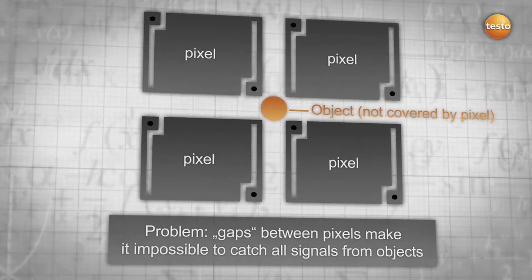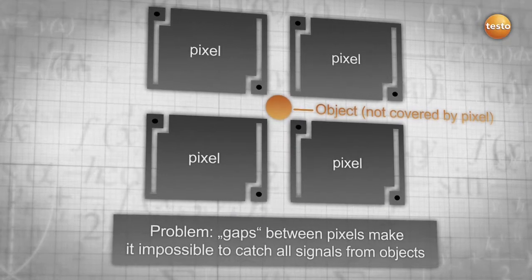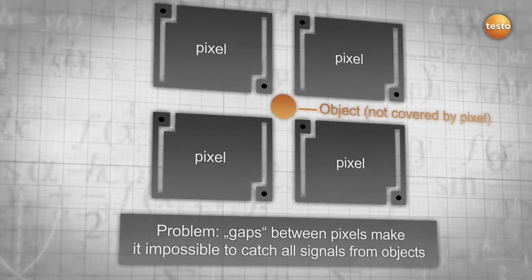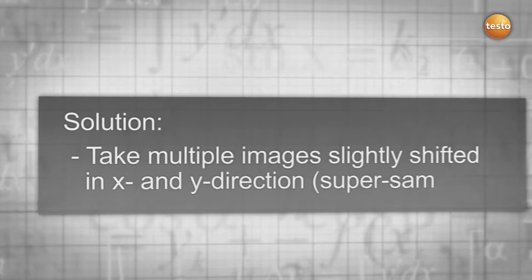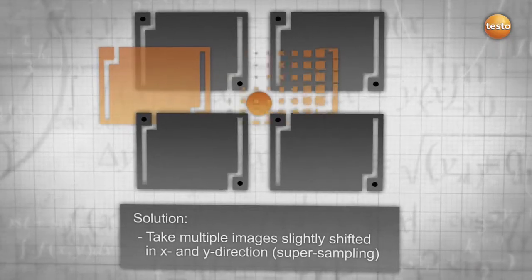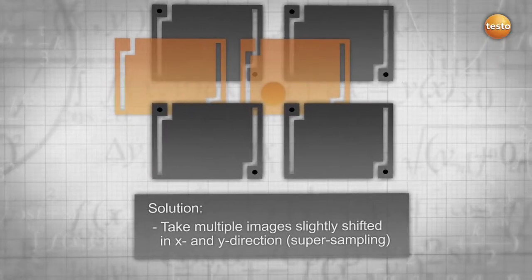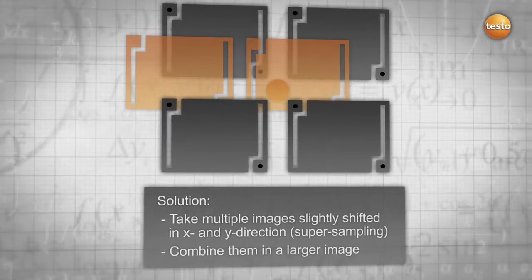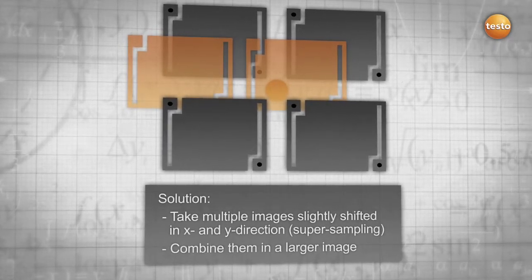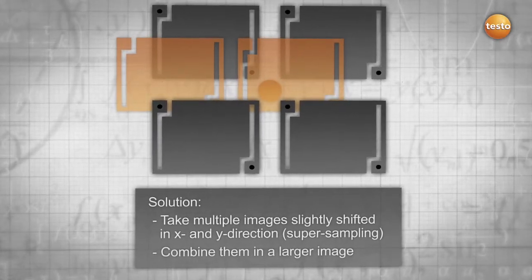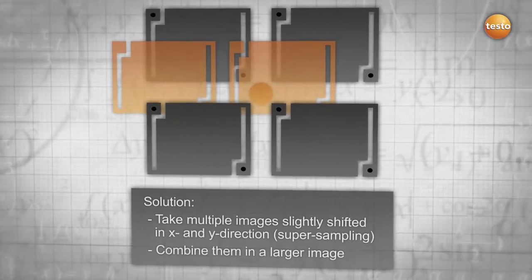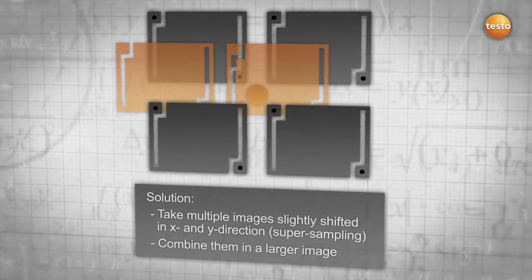One of the main problems with detectors are the gaps between each pixel. Through these gaps, it is almost impossible to catch all signals emitted by objects laying in between pixels. Supersampling provides a solution to this problem. Since the advanced technology takes multiple images, slightly shifts them and combines them into one larger image. This technology enables you to record more signals and results in more accurate measurement and more pixels.